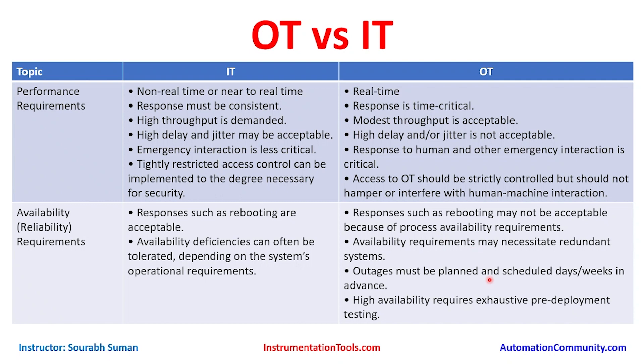Availability requirements may necessitate redundant systems in OT. To maintain availability, we create redundant systems so that if one system is lost, we can switch to another. Outages must be planned and scheduled days or weeks in advance. We need to plan when we can do a planned shutdown of servers, workstations, and other control systems — finding a maintenance window during a process shutdown to reboot or service the control system.